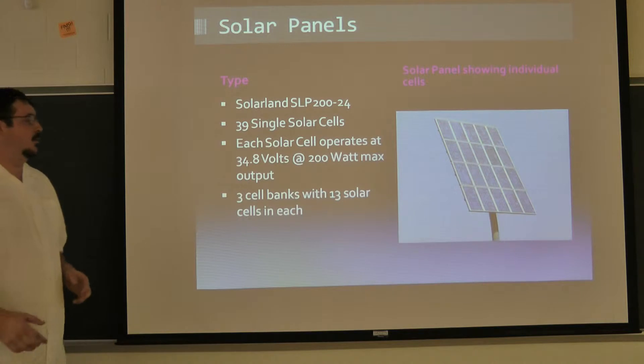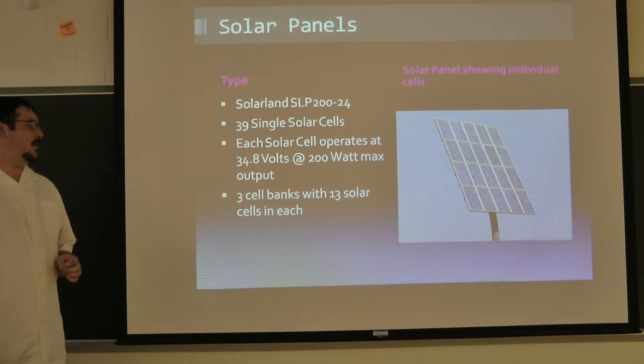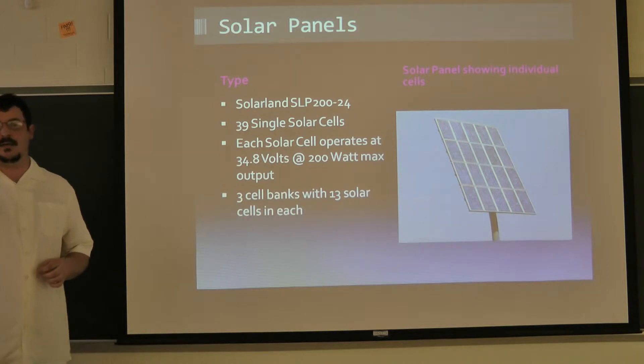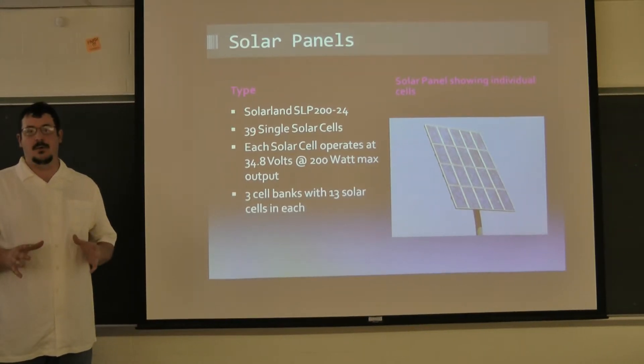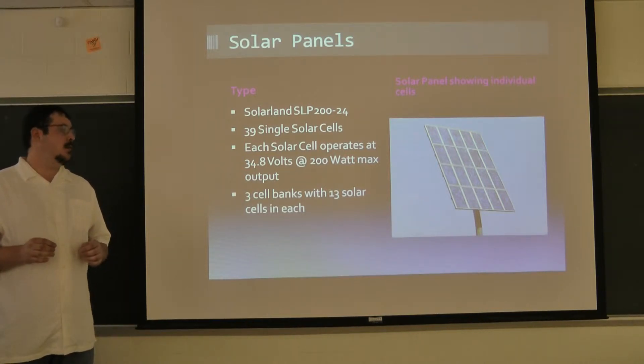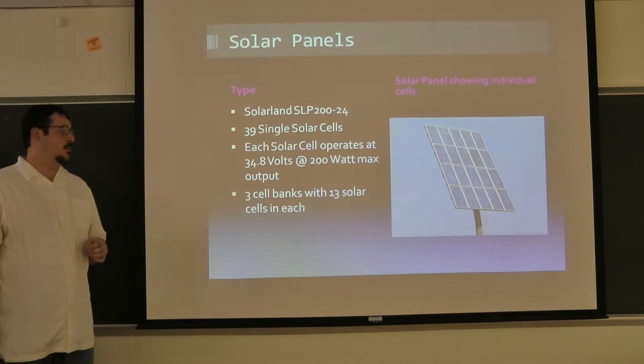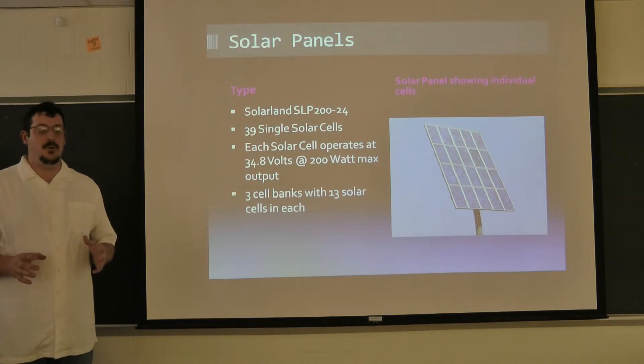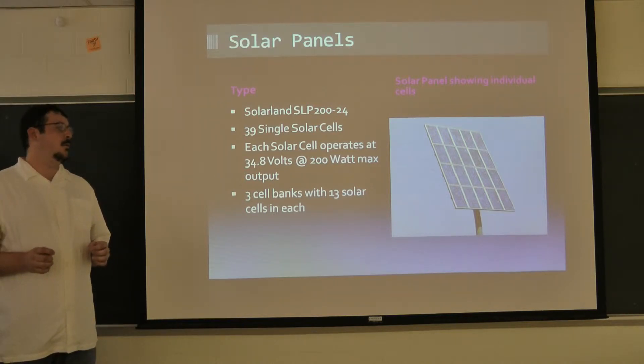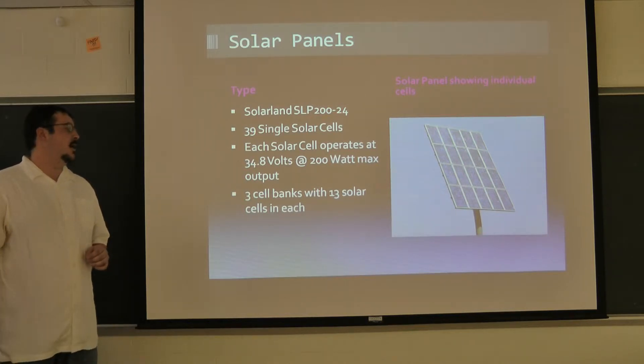We are going to use 39 individual solar cells, each with a 200-watt peak max output. We will take 13 cells and create a cell bank by putting them in series, so each cell bank output will be around 452 volts, which is around the peak operating voltage for the inverter.